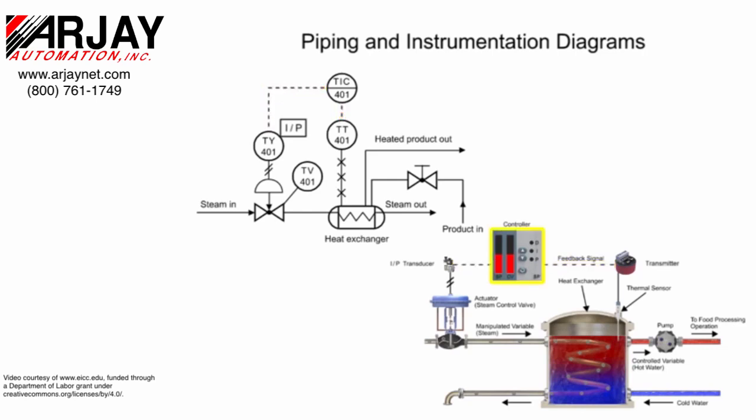The controller and indicator is the instrument where the transmitter sends an electrical signal and is shown in the functional identifier at the second and third letters I and C. Balloons with a solid dividing line indicates that the instrument is board mounted.